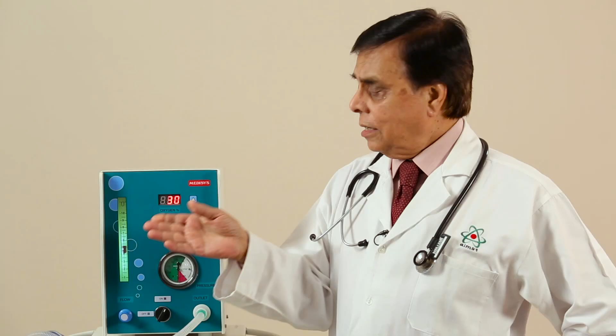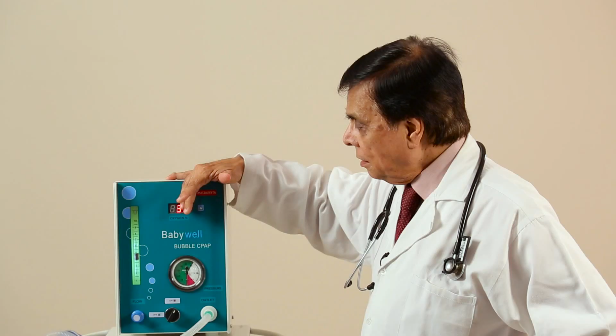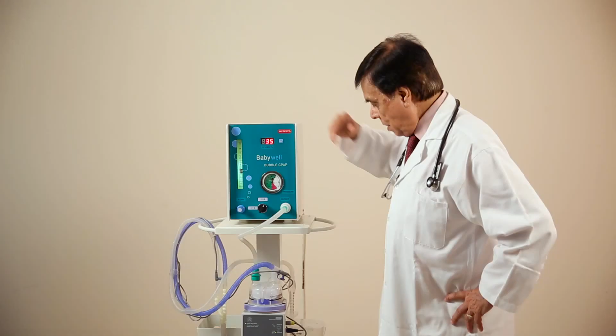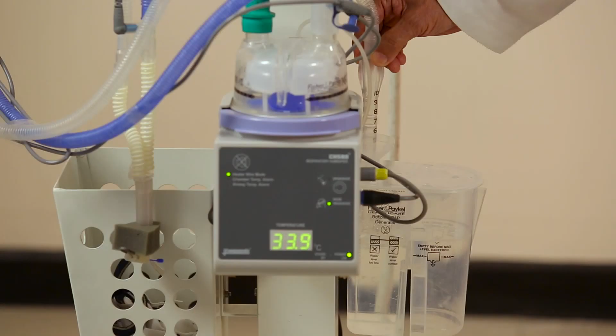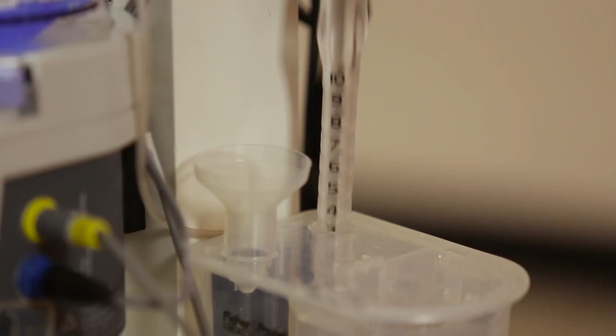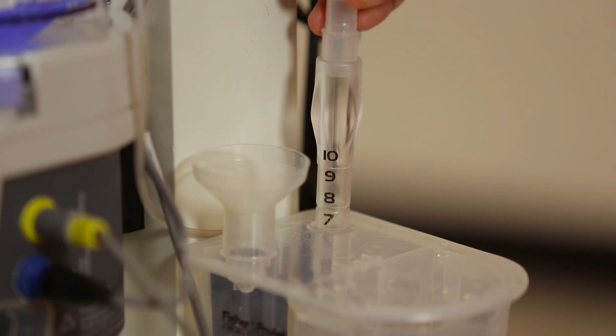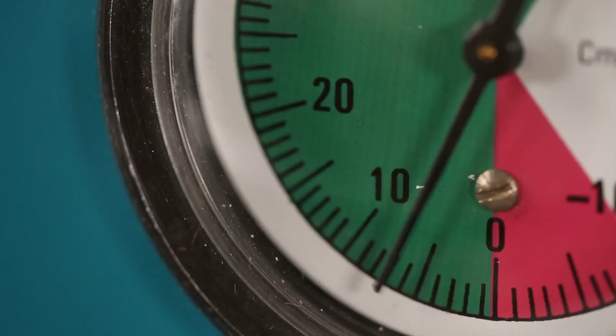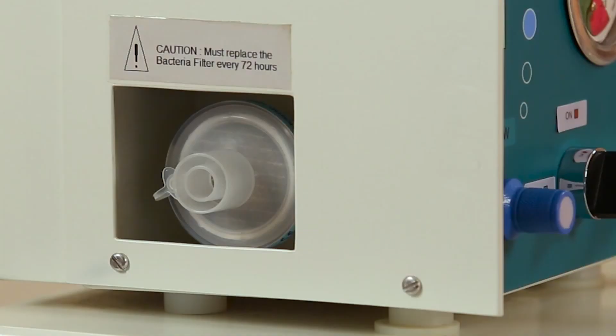And this machine is not only simple to operate. What you have to do is get the patient, get the airway, and simply put the machine on from the off position, decide the oxygen fraction, and you get it here. So it is digitally displayed here, and it is very simple, as you all know, to provide the CPAP by just dipping this in and out, and then how much CPAP you are giving you can read from this dial. This is our machine with a simple baby circuit which is low resistance, and then we have a safety device which is very important: if the electricity fails, which happens very often in our country, particularly in remote areas, the machine will continue giving 40% of the oxygen. Now I think this is one of the very important parts of the machine, very simple to handle, even the nurses can do it, and this is our Babywell CPAP machine, bubble type.